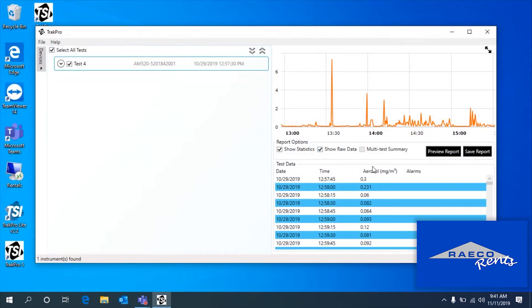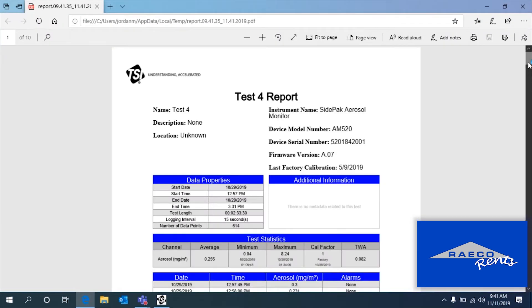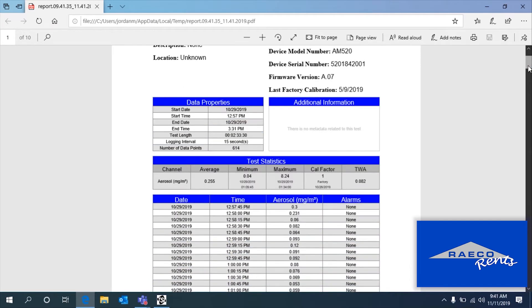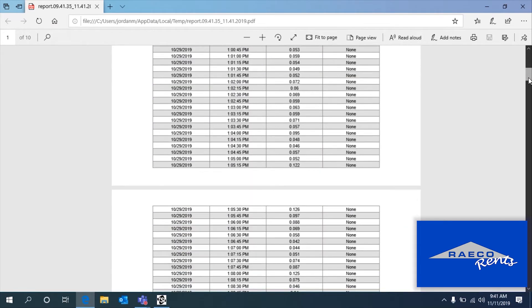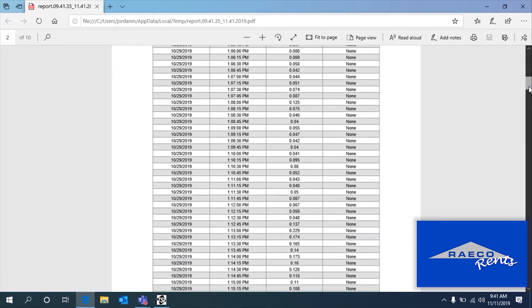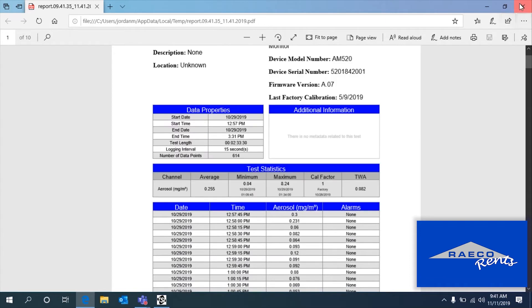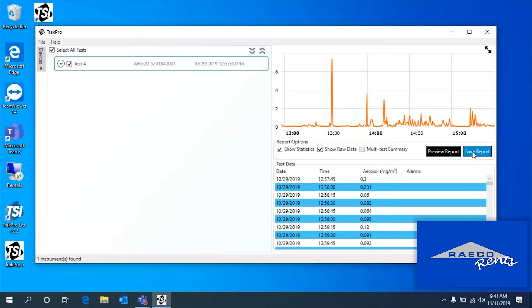If we enable this option, then it's going to show all this additional data. Let's preview that report again. Now it shows a little summary and then, almost like an Excel file, you'll get your data points at each data log interval in the report. Now if we want to actually save it, we just click on the save report button, and it's going to save a PDF of our report.